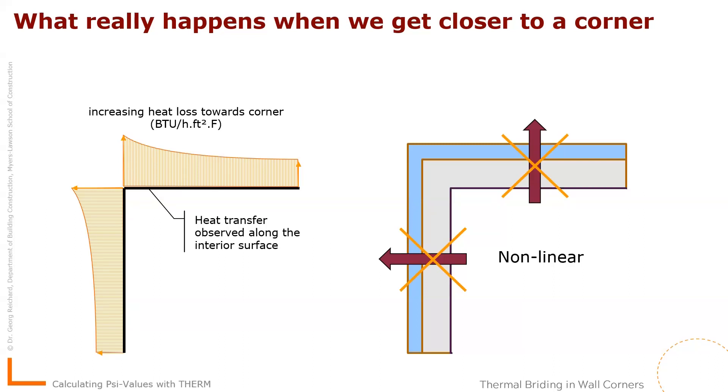So how can we capture that additional loss? Well, this is where THERM comes in. So THERM allows us to define a U tag for a boundary, and with this U tag we can calculate an average heat transfer along the tag boundary. And the average U value in total comes to, because it's now a constant U factor, it becomes in its total the same amount as the real flux, the one that increased towards the corner constituents.